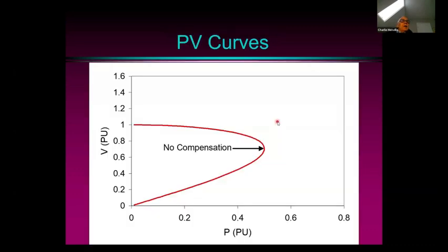So here we have what we call the PV curve, which is the voltage at the load delivery point versus the amount of power that is delivered. And you can see as you reduce the resistance, the amount delivered gradually increases until you reach a certain maximum, and then it decreases again.